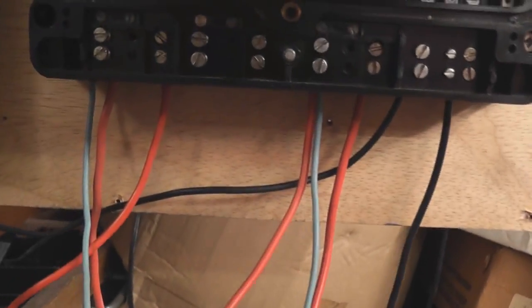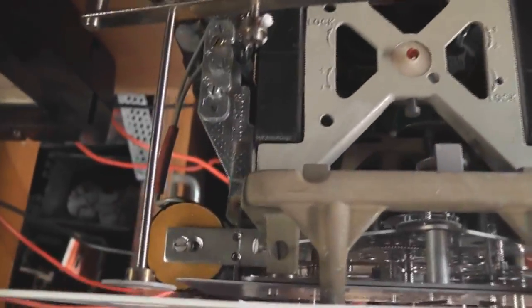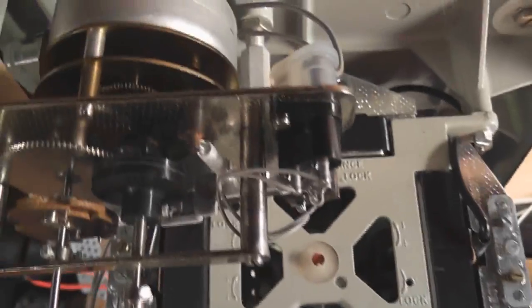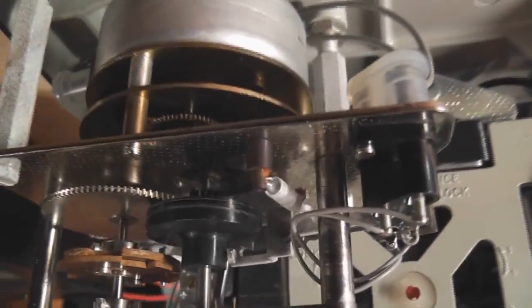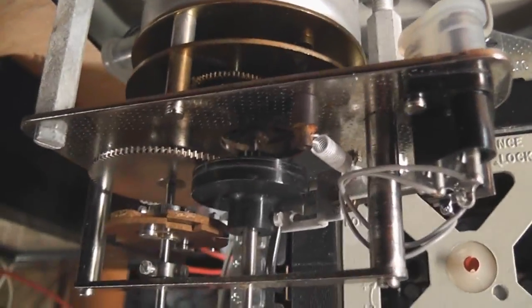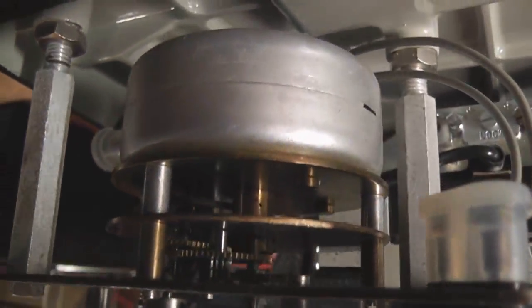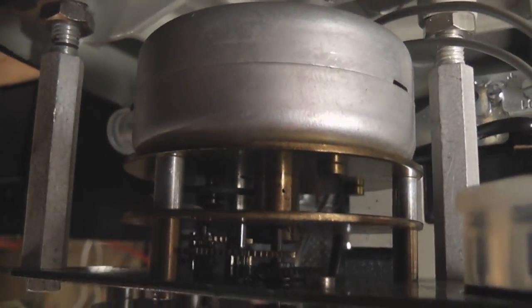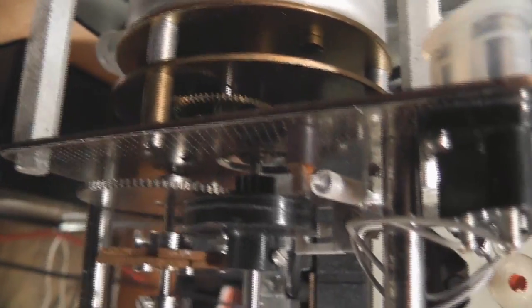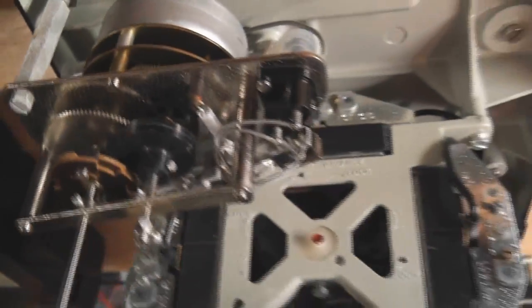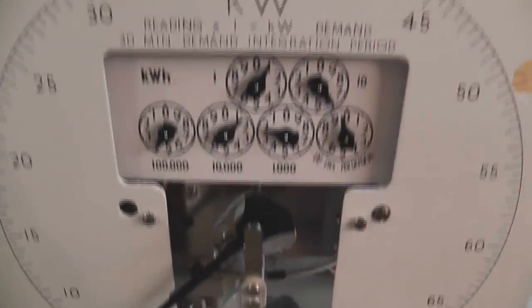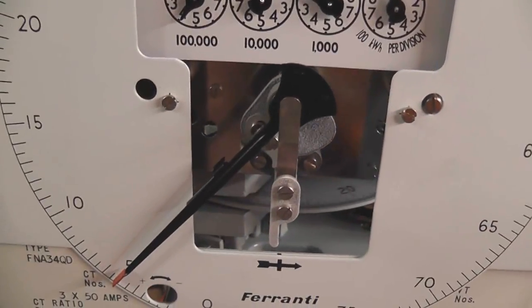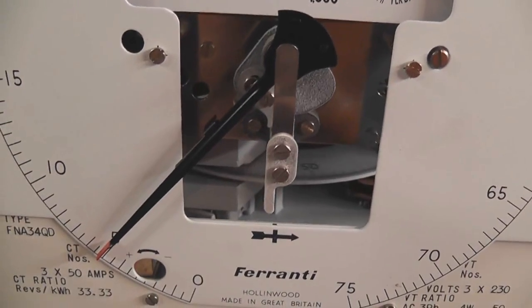I've connected the MDI meter up, there needed to be a jumper from the active to an extra terminal to activate the coil which sits on the side here. There's a coil there but it goes via the clockwork mechanism which sits here and it's got a switch which, 30 minutes, there's a synchronous motor. It has a switch which drops the pointer out which pushes the main needle up in 30 minutes intervals on this particular device.